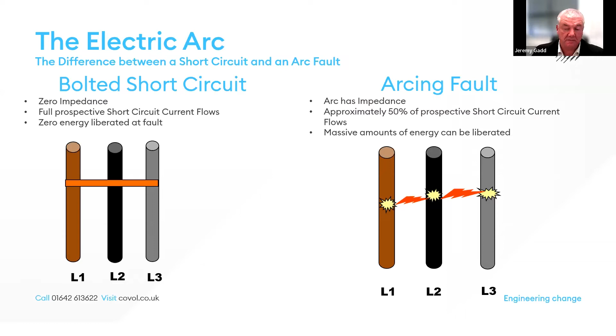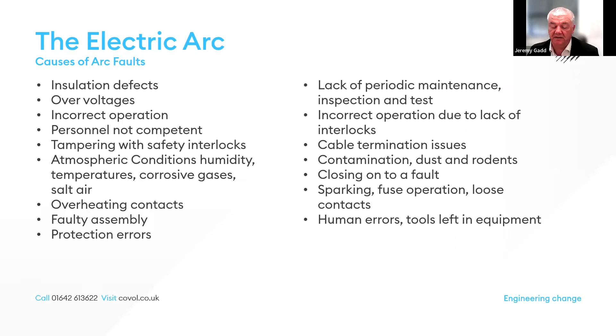There are numerous causes that can lead to an arc flash event, and I've listed some of these on screen now: staff competency and low or no awareness of the hazards, poor maintenance and improper conditions all contribute to the cause. So generally I wouldn't say it's ignorance, but it is around poor knowledge, poor maintenance, and just a general lack of information relating to arc flash hazards.